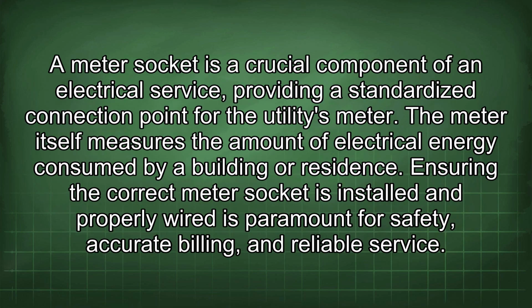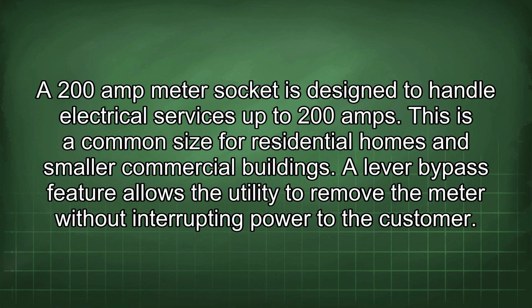A meter socket is a crucial component of an electrical service, providing a standardized connection point for the utility's meter. The meter itself measures the amount of electrical energy consumed by a building or residence. Ensuring the correct meter socket is installed and properly wired is paramount for safety, accurate billing, and reliable service. A 200 amp meter socket is designed to handle electrical services up to 200 amps. This is a common size for residential homes and smaller commercial buildings.